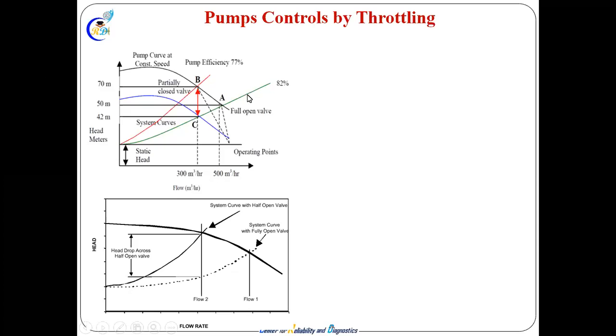So what is the problem with throttling? We are increasing the system resistance, which means we are increasing the frictional head. This is the red curve. The static head remains the same, whatever the height is, that's it, it has nothing to do with it. So the system curve is increasing, and point A cannot go through this system curve, because we cannot change the flow along it. We want less flow, so the flow will go here. The flow will be 300 at this point, and your system curve has changed to this red line. It means you have gone against high pressure and you are losing much more energy.